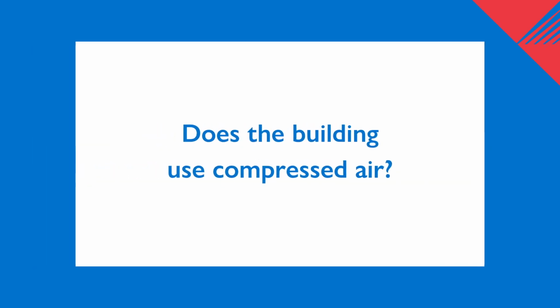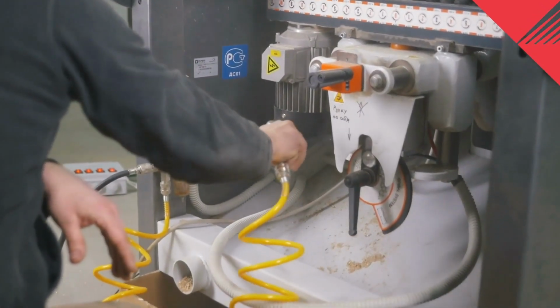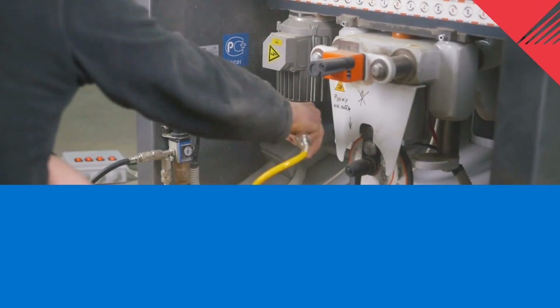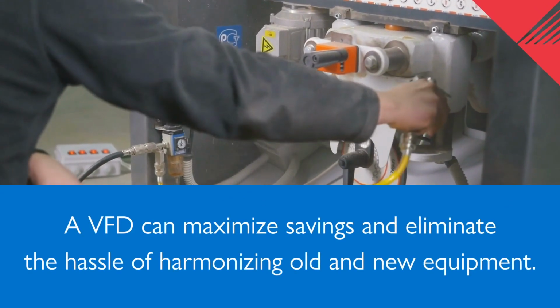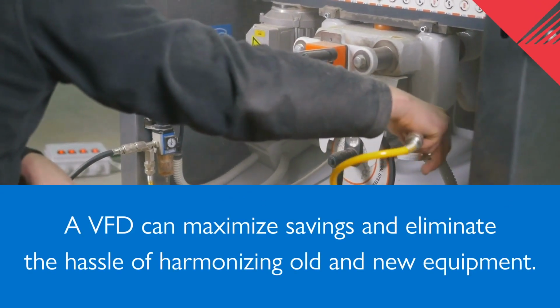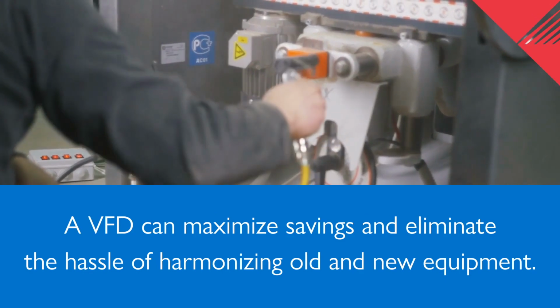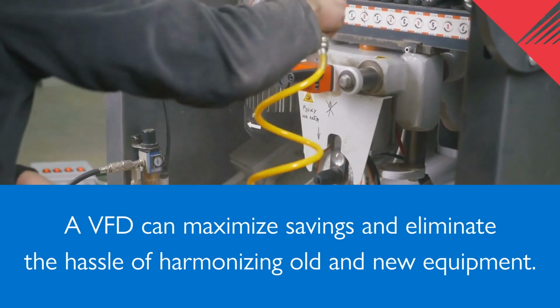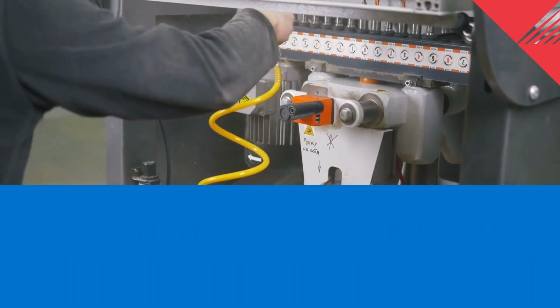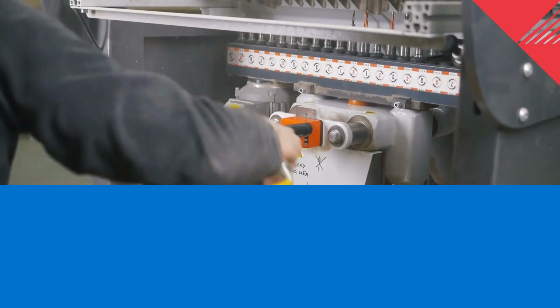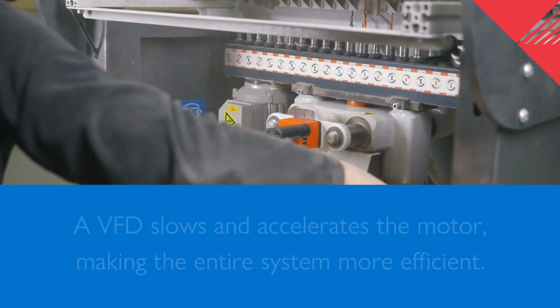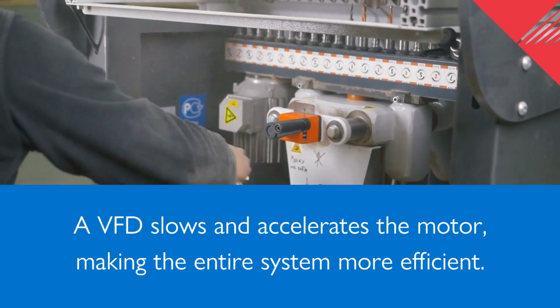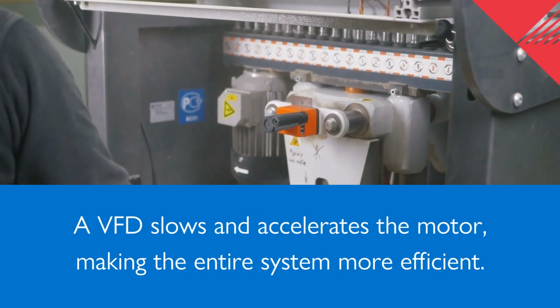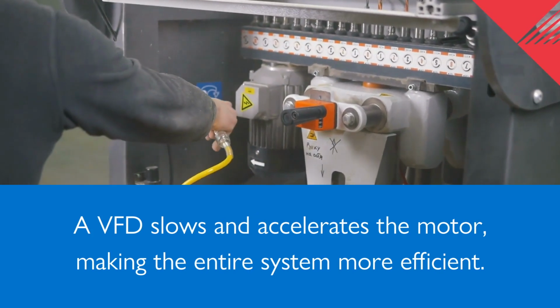Does the building use compressed air? New compressors are costly and may not integrate well into existing controls. A VFD can maximize energy savings on the existing compressor and eliminate the hassle of trying to harmonize old and new equipment. The frequent starting and stopping of compressors uses a lot of energy. A VFD slows and accelerates the motor, making the entire system more efficient for extra savings above the associated decrease in energy use.